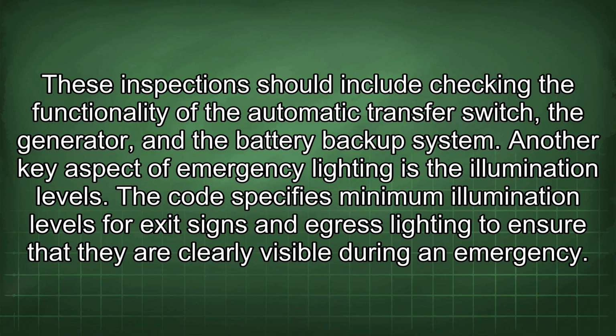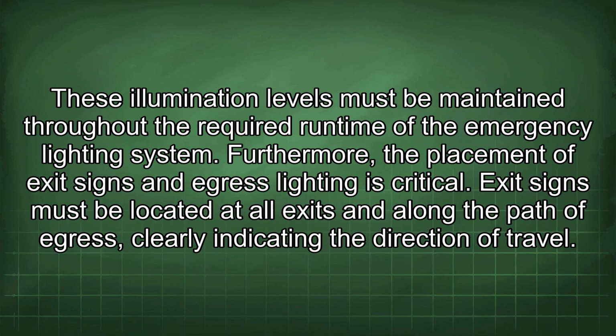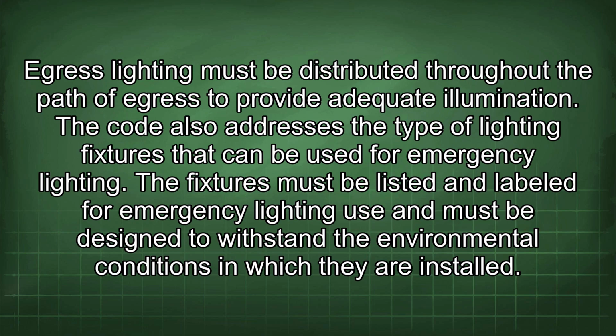Another key aspect of emergency lighting is the illumination levels. The code specifies minimum illumination levels for exit signs and egress lighting to ensure that they are clearly visible during an emergency. These illumination levels must be maintained throughout the required runtime of the emergency lighting system. Furthermore, the placement of exit signs and egress lighting is critical. Exit signs must be located at all exits and along the path of egress, clearly indicating the direction of travel. Egress lighting must be distributed throughout the path of egress to provide adequate illumination.